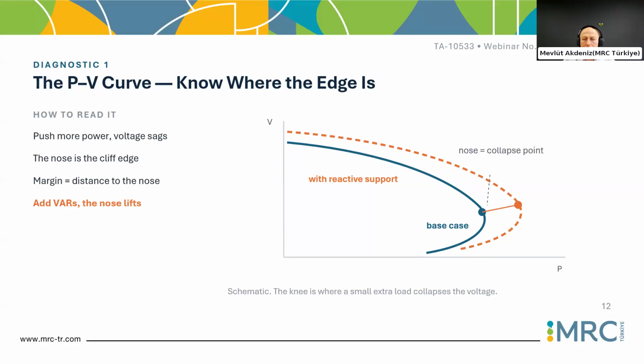So we can also scan, try or implement N-1 analysis, and if the curve jumps relatively too much, it means that even though the N-1 load flow converges in your typical analysis, during any transients you have very little margin to move or step from the pre-fault condition to the post-fault condition in real cases. I mean, the load flow may converge. It's a simulation. It just simulates the two points shown on the plot, the edge points. So numerically they are balanced and converged, and the error is practically zero. But the transition from one point to another in the transient domain may require some transient analysis, or you can just scan and image this critical unstable transition point via very simplified load flow solutions called PV curves.